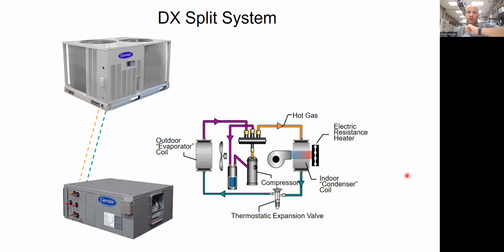All right, a DX split system. When we use the term DX, that means direct expansion. Almost everything you're familiar with is a direct expansion system. What that means is the refrigerant expands inside the evaporator coil that's in the airstream. Something that would not be a direct expansion system is a chiller, right? The expansion of the refrigerant is happening over at the chiller. It's not happening in my airstream. I have chilled water in my airstream cooling down my air.